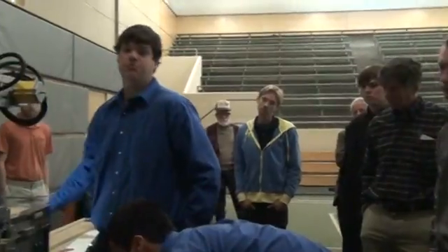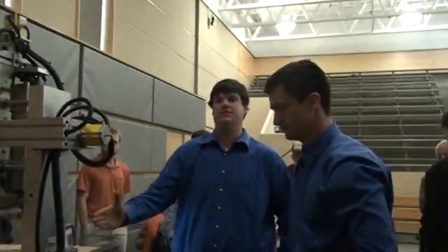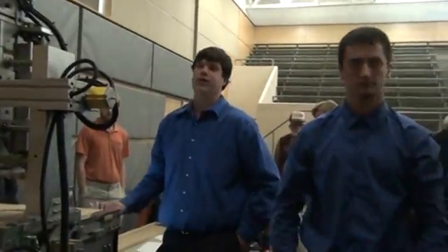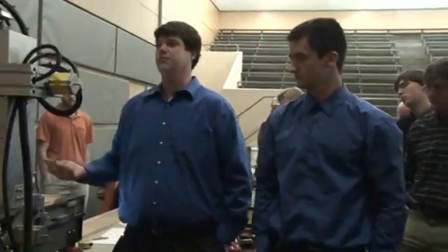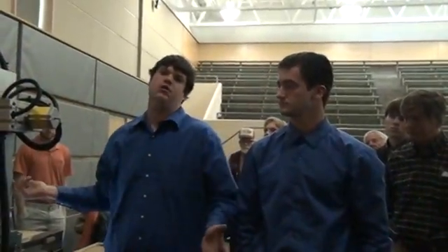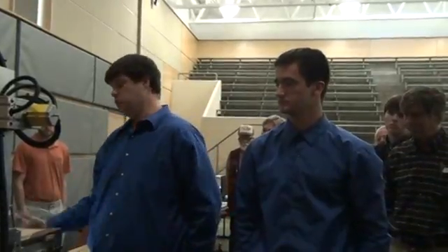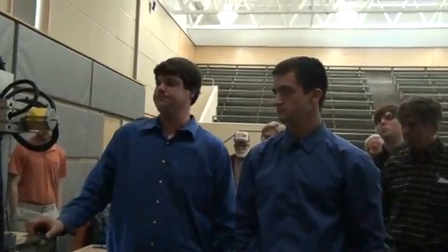So it'd come up as X plus over travel, and it'd show up right on your screen, so you knew exactly what happened at that moment, instead of, oh, it hit an emergency. We know because we've been working on it, we built it. Now somebody might accidentally come up and hit this Z, not realize they're on the limit, and wonder why they can't do anything. Whereas if it was wired that way, it would say that. So that's one advantage of doing it that way.